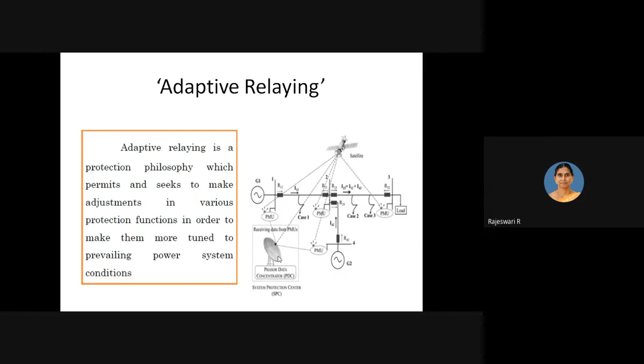Analytically, power system engineers derive the value to be set in all the relays, and with respect to that set value only, the protection schemes have traditionally operated against an abnormal condition. Whereas in adaptive relaying, for the prevailing power system condition, based on real-time data, the relay functions can be easily modified, and accordingly the protection system can operate. So that kind of adaptive relaying is possible.